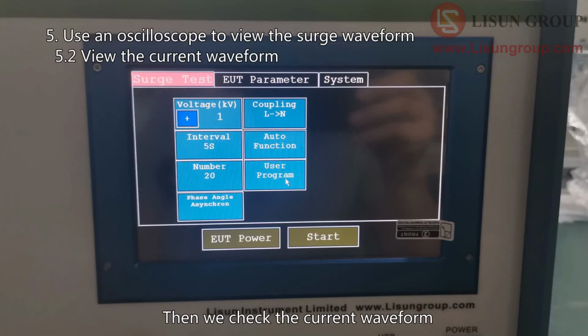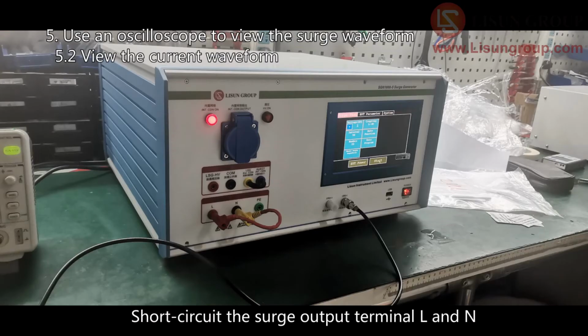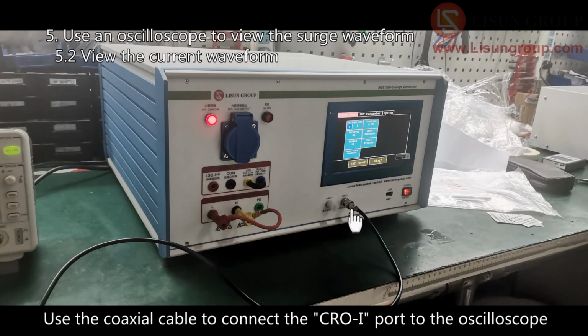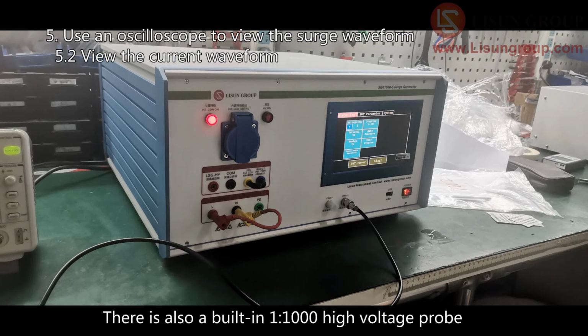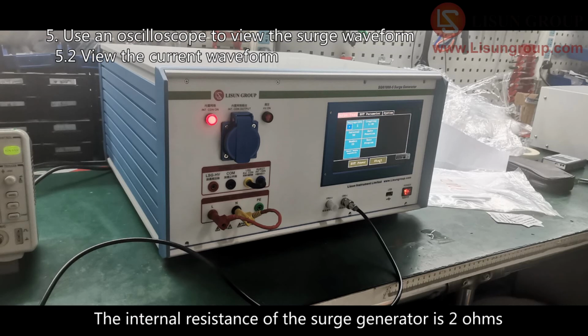Then we check the current waveform. The setting of surge generator is the same as when viewing the voltage waveform. Short circuit the surge output terminal L and N. Use the coaxial cable to connect the CROI port to the oscilloscope. There is also a built-in 1 to 1000 high voltage probe. The internal resistance of the surge generator is 2 ohms.